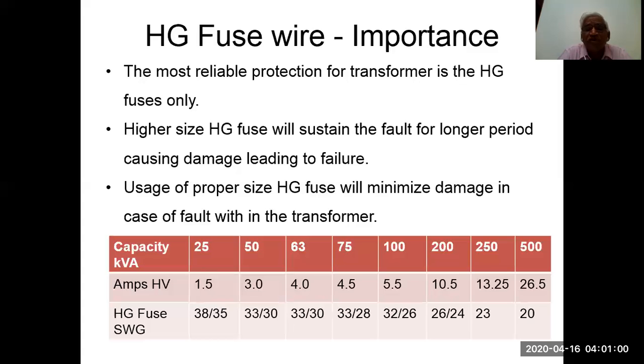You should always check the capacity of your transformer and the amperes as given on the transformer, and see that they match the figures we have given here. The HG fuse standard wire gauge, you have to buy it, keep it in stock, and replace it whenever there is a failure of the fuse. But please don't use PVC wire of unknown standard or put in a bigger size. A bigger size will damage the transformer.